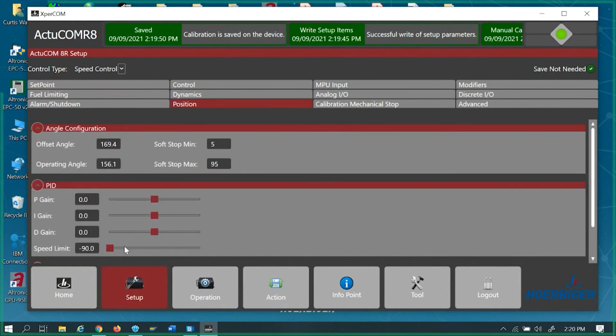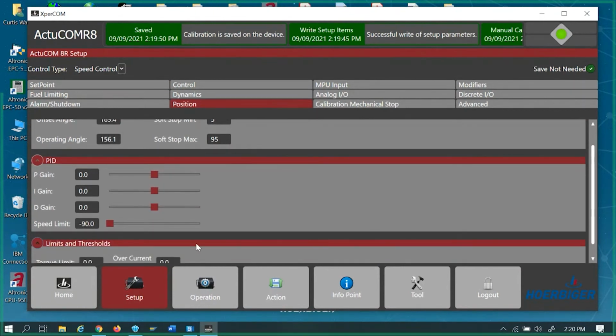Another thing I think is kind of important on these PIDs, I haven't really had to mess with those hardly at all. But the one thing I have messed with, if you notice, this thing seems pretty violent. Whenever you energize it or run enable, you see that thing just slap open or slap shut. Y'all seen that out there in the field? Well, I found if I set this thing at a -10, all of that goes away. It just goes so much smoother.